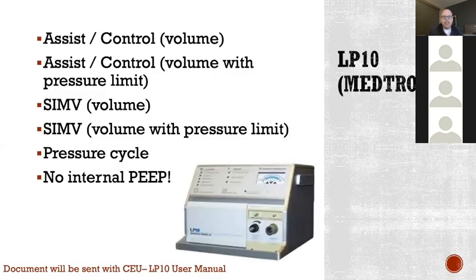The first one is the LP10 from Medtronic. This ventilator can do assist control volume, and it can do SIMV volume, and it has something called a pressure limit. What this means is it is only volume ventilation on this vent. It cannot do pressure modes of ventilation. Well, what did we say is nice sometimes in sick lung ARDS patients? Pressure modes of ventilation, right? So unfortunately, these ones can't do it. But they do have a pressure limit on them, so you can set the maximum amount of pressure.